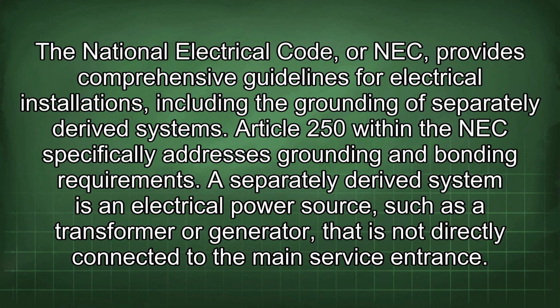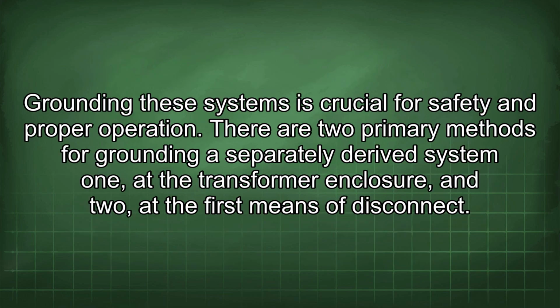The National Electrical Code, or NEC, provides comprehensive guidelines for electrical installations, including the grounding of separately derived systems. Article 250 within the NEC specifically addresses grounding and bonding requirements. A separately derived system is an electrical power source such as a transformer or generator that is not directly connected to the main service entrance. Grounding these systems is crucial for safety and proper operation.